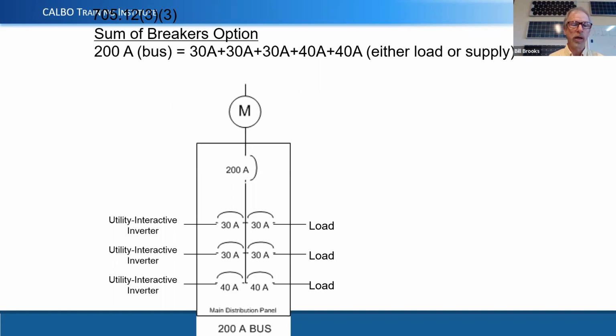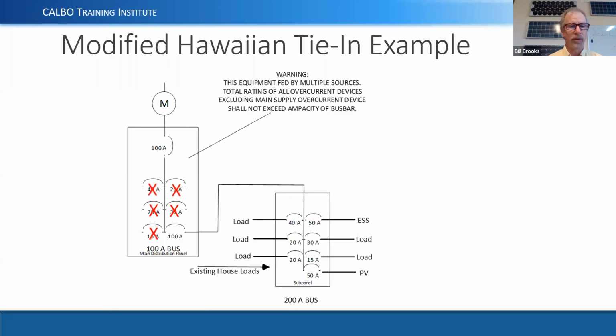So very, very important item that a lot of people don't know about because they're so used to using the 120% rule. So I call this the modified Hawaiian tie-in method because basically what we do is we take all our breakers out of that main panel, we just stick a 100 amp breaker in there, and then we come over to a 200 amp panel, right? So we feed that 200 amp panel with a 100 amp feeder breaker out of the main panel. All the rest of the circuits are pulled out of that panel and put into this. And now we can double the amount of PV. So we could have a 50 amp PV and a 50 amp ESS in here, no problem.